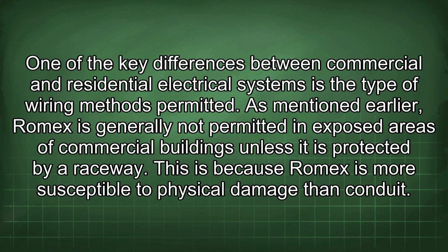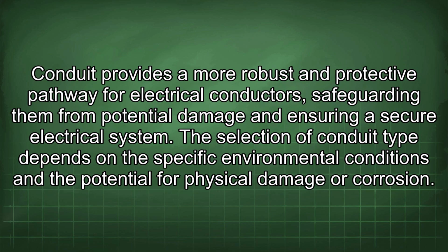One of the key differences between commercial and residential electrical systems is the type of wiring methods permitted. As mentioned earlier, Romex is generally not permitted in exposed areas of commercial buildings unless it is protected by a raceway. This is because Romex is more susceptible to physical damage than conduit. Conduit provides a more robust and protective pathway for electrical conductors, safeguarding them from potential damage and ensuring a secure electrical system.